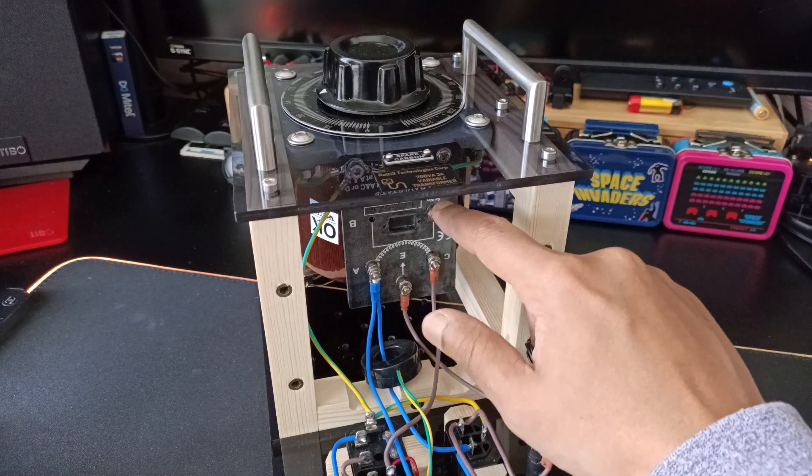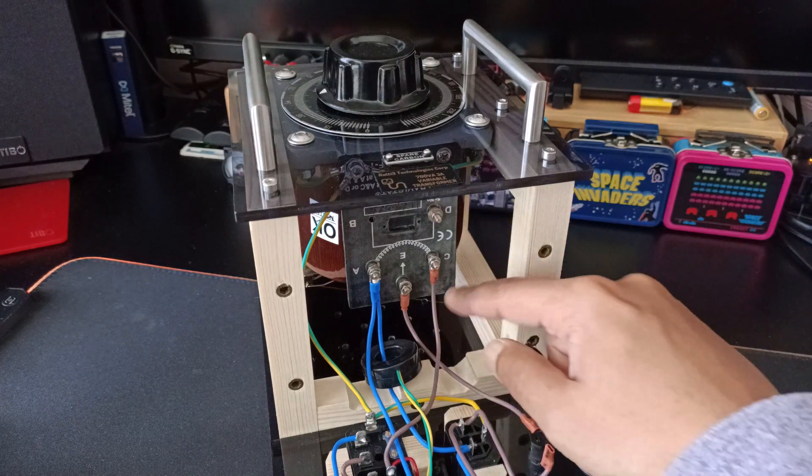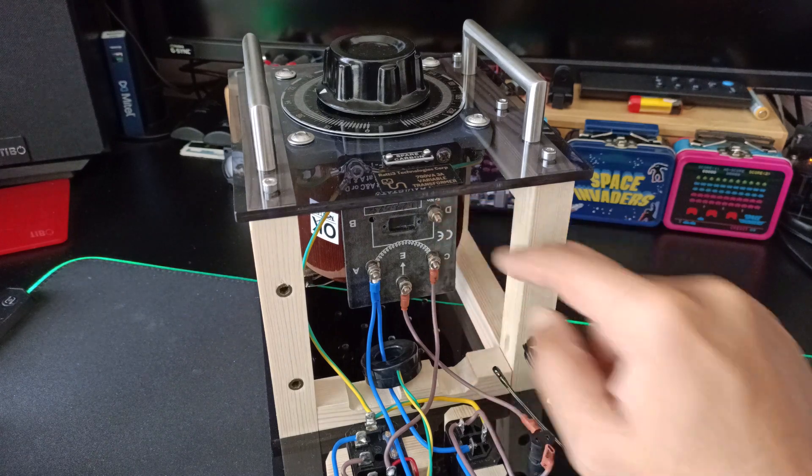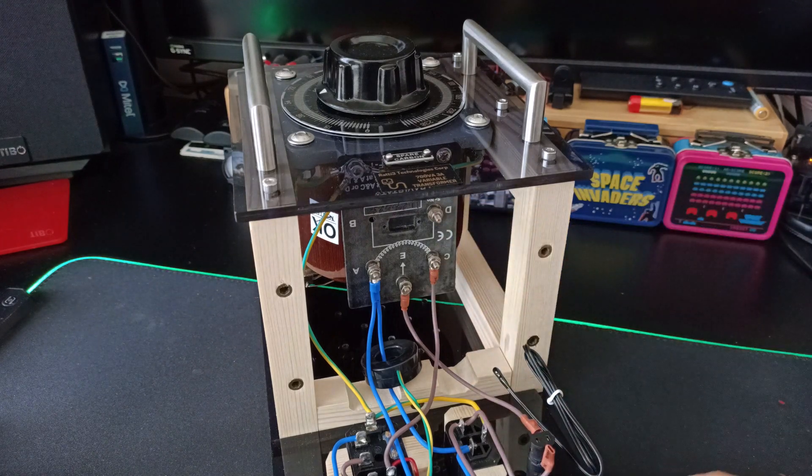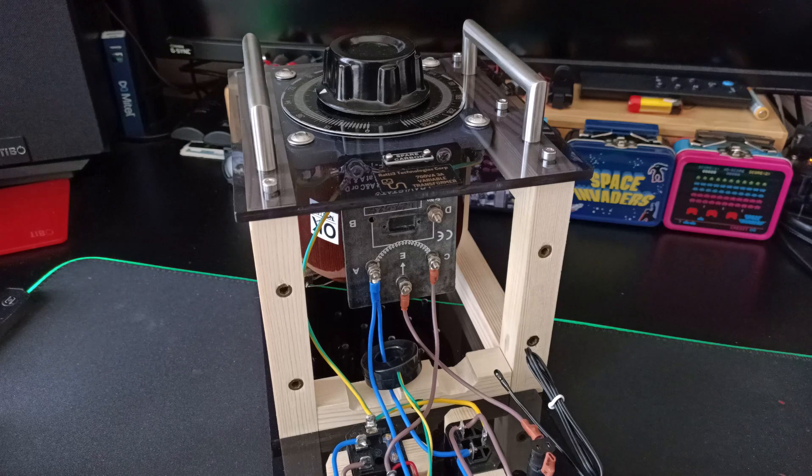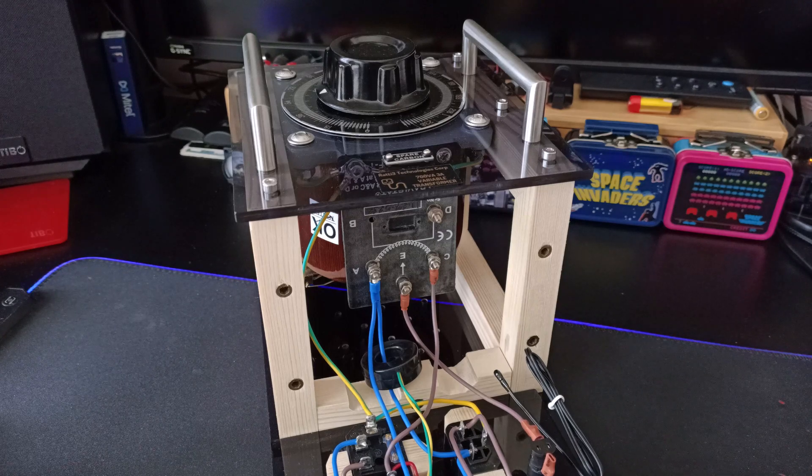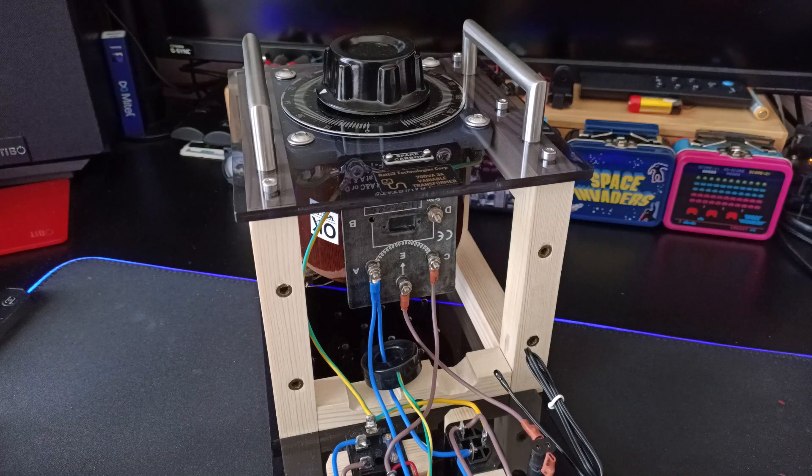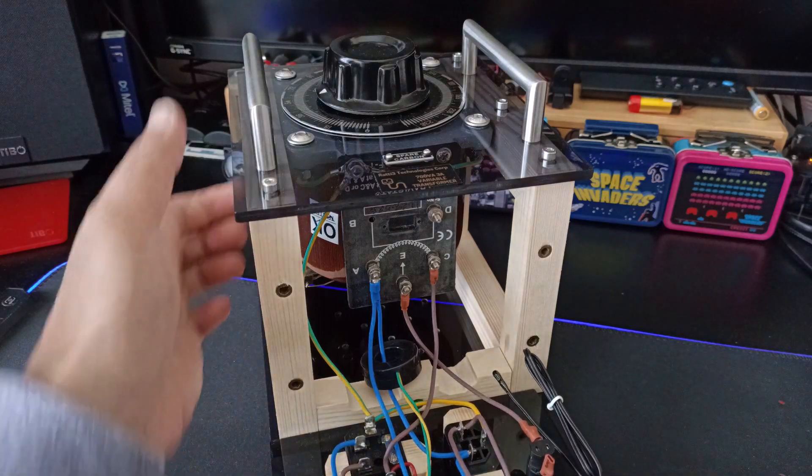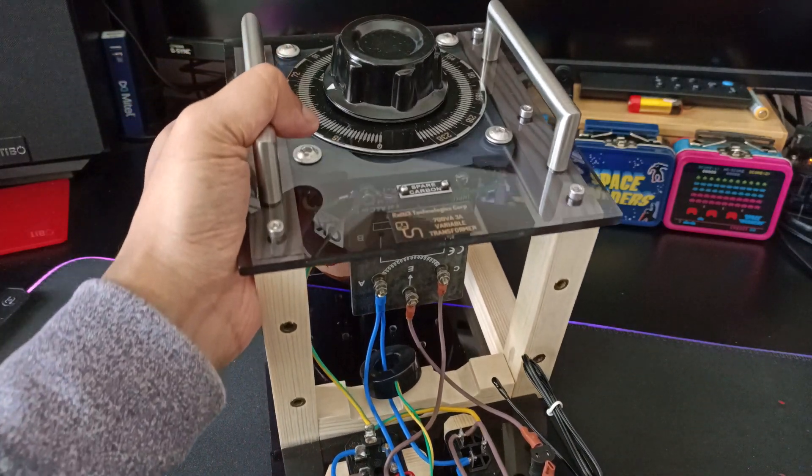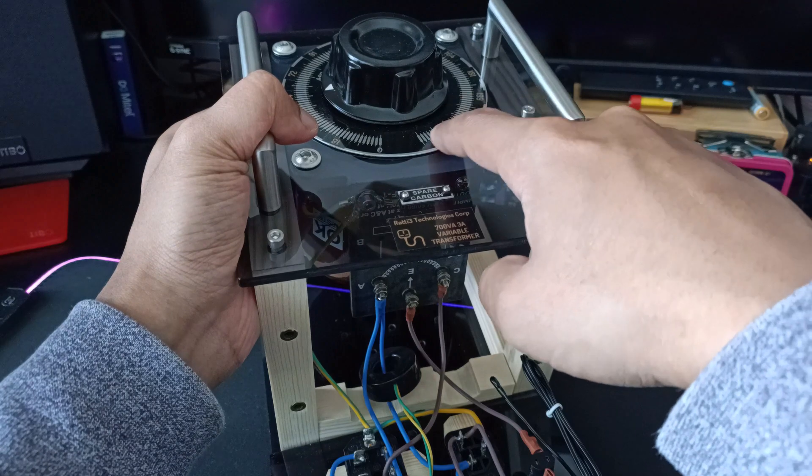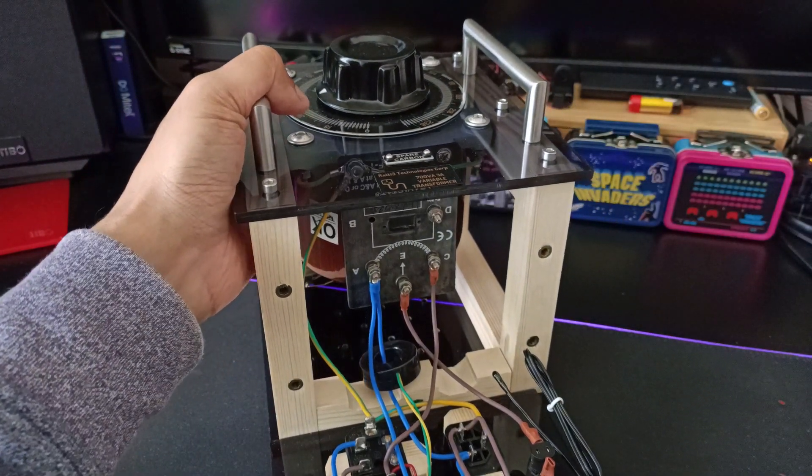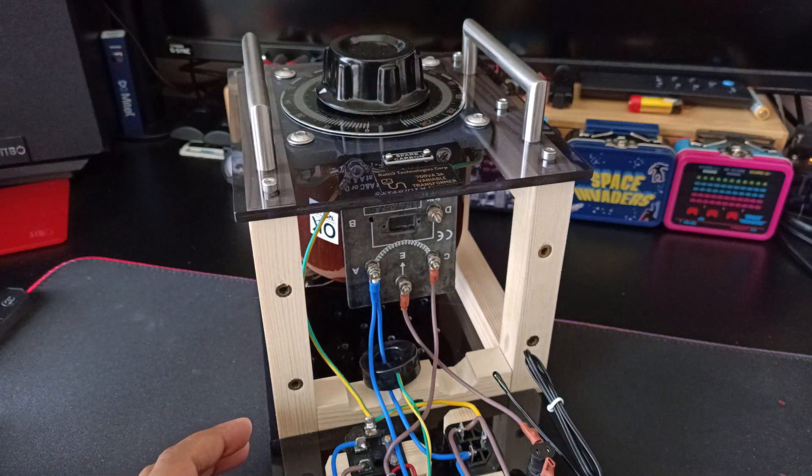I haven't connected to terminal D. If you connect the live hot wire to D, it means you get 270 volts out. I don't need the 270 volts. I just want the line voltage at the maximum. So I have made changes and put some labels on to show the output voltage accordingly on the analog scale.